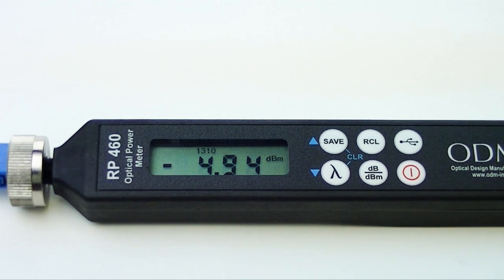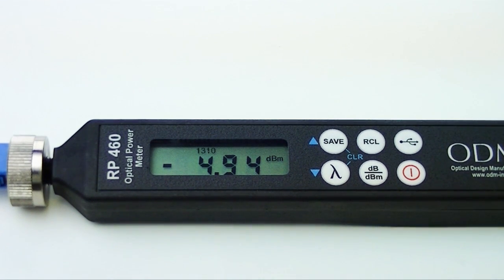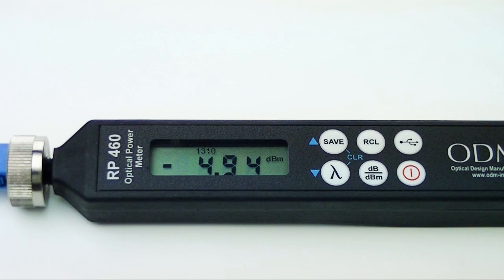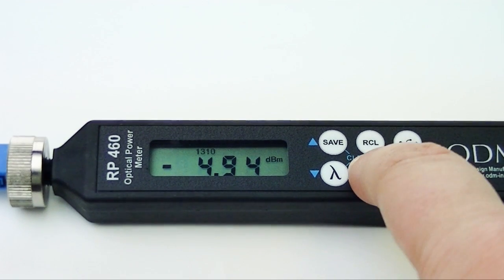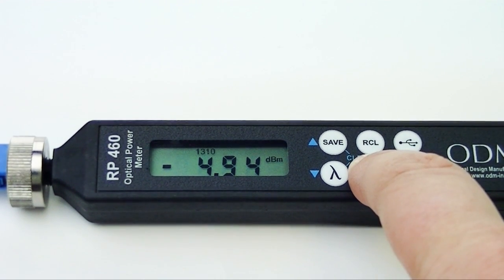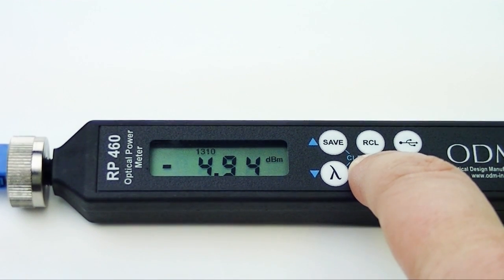With your reading between negative 3 and negative 5 DBM, you can now set your reference by holding the DB-DBM key for 4 seconds until you hear a second, slightly longer beep.